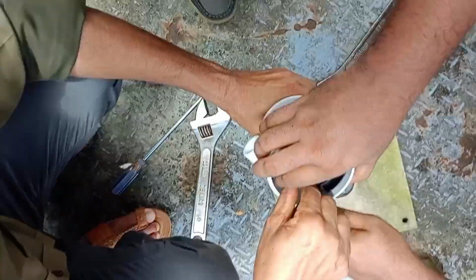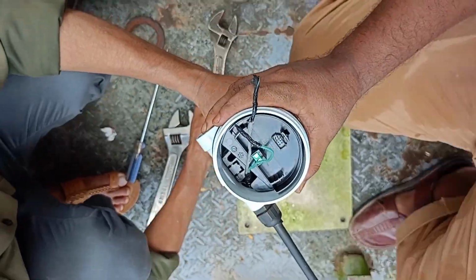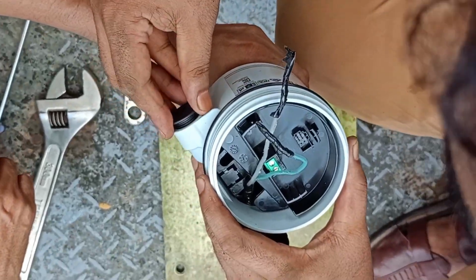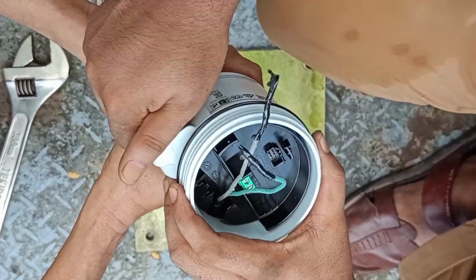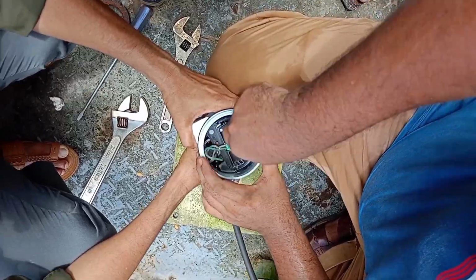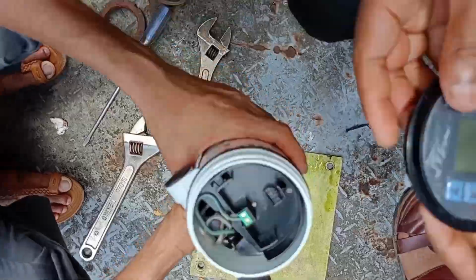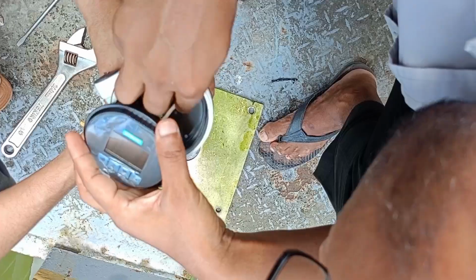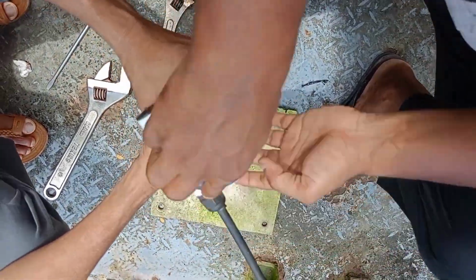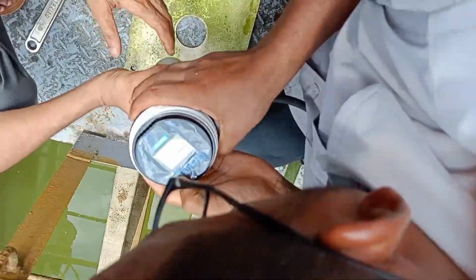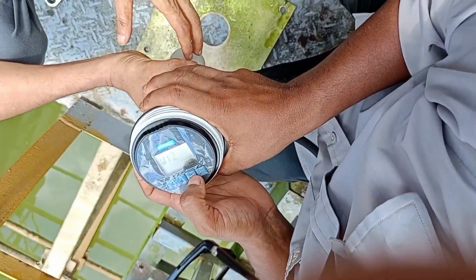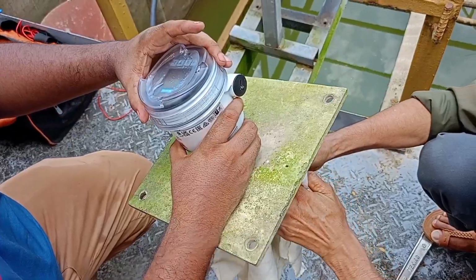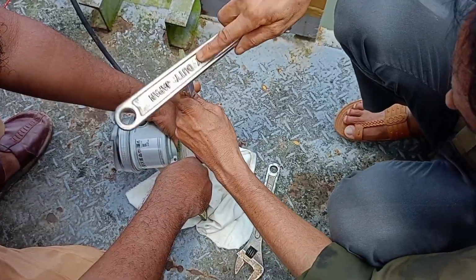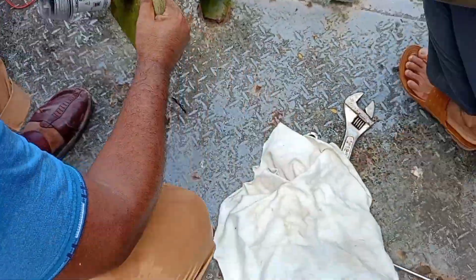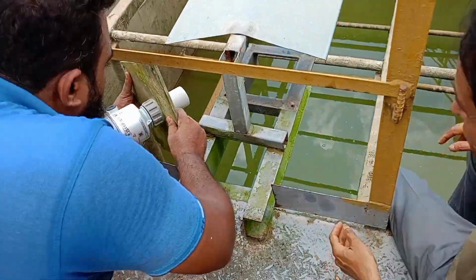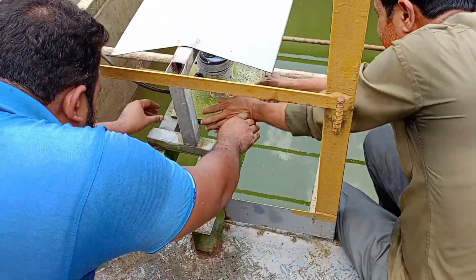The base was tightened, so we loosen the base. We use this base to install the new one. It is on our tank, the transmitter part, connecting the power supply unit, the power supply connection to the new one. Now the connection is okay, and finally we tighten the sensor unit and we install the transmitter on the tank base.